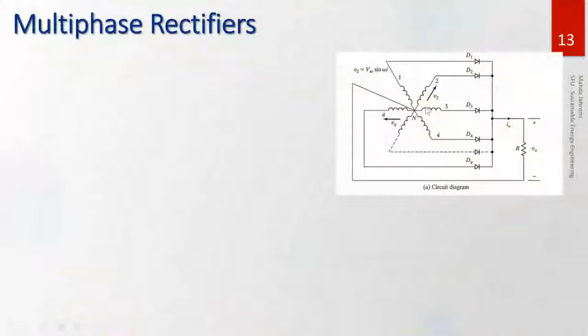And the reason for that is not only that you can get higher powers when you increase the number of phases. If you're dealing with, for example, 20 kilowatts with one phase, the voltage can only go up to 120 volts. Let's just say, for the sake of argument, this is almost 100 volts. The current in this case will be 200 amps. 200 amps is a lot. When you go to 200 kilowatts, you'll end up with 2000 amps for one phase. And this is too much for one phase. The size of the cables, the equipment, it just basically does not make sense.